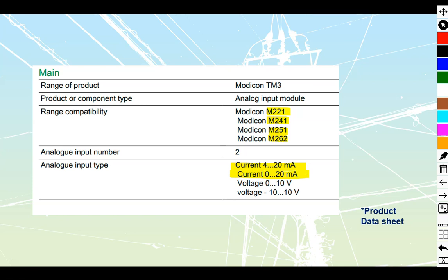For those that have never used a signal before and are wondering why we start with a base range of 4 to 20 milliamp, the 4 to 20 milliamp really just allows us to monitor that whatever we have is still going to be operational. Whereas with a 0 to 20 milliamp, if you get 0 milliamps, it might be because the signal is putting out 0 milliamps, whatever it is at a minimum or a maximum, or it could also be because the cable is cut. A 4 to 20 milliamp is going to let you know when you lose connection with the device because your current will drop below that 4 milliamp minimum threshold. So it just gives you a better style of monitoring. However, because you're only across 16 milliamps total, you do have a smaller resolution that you're able to measure.